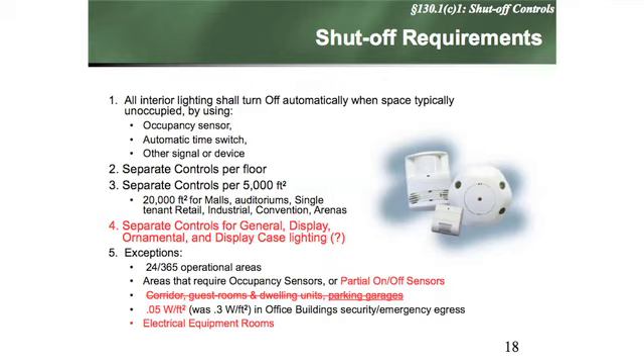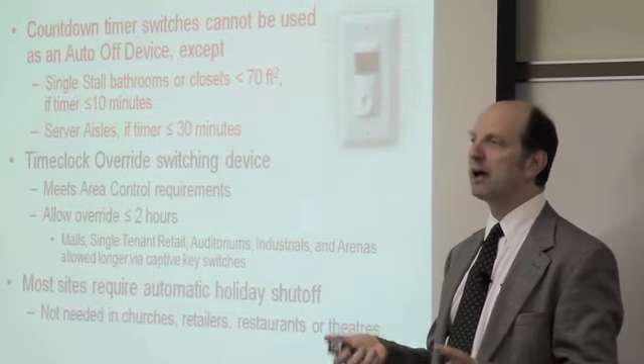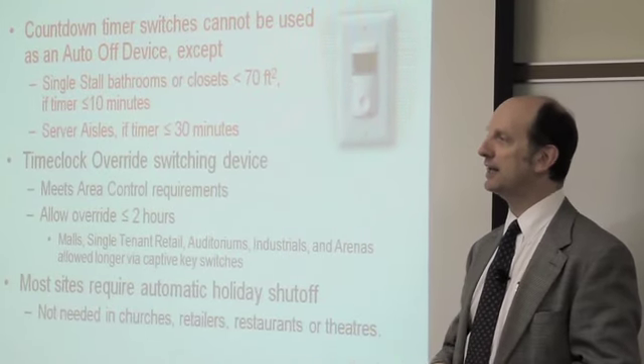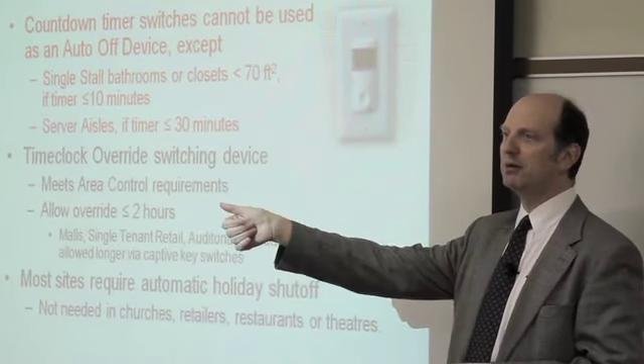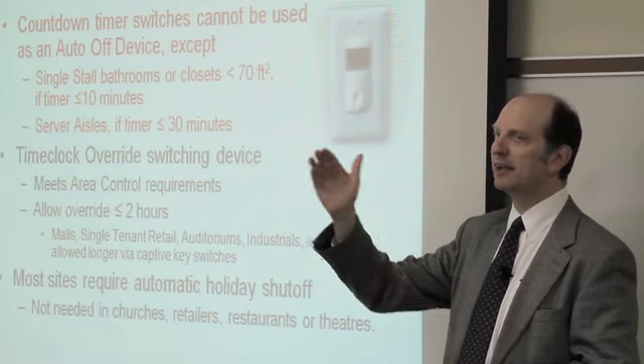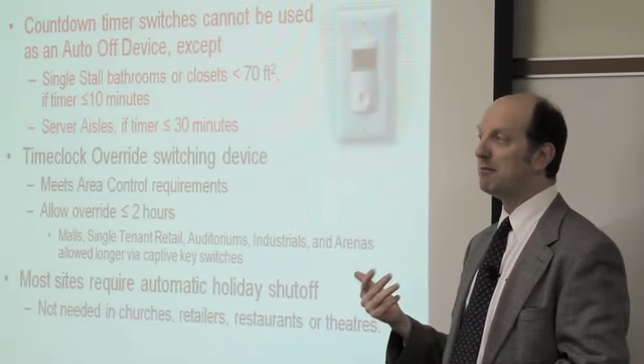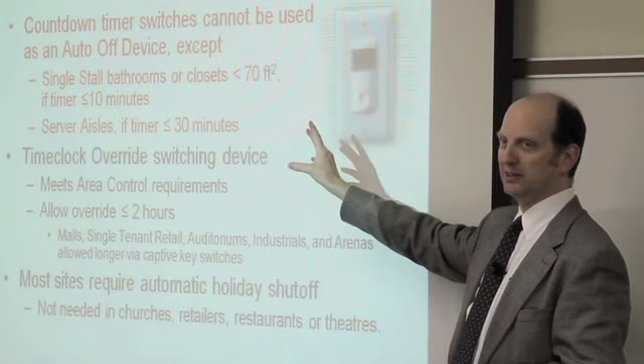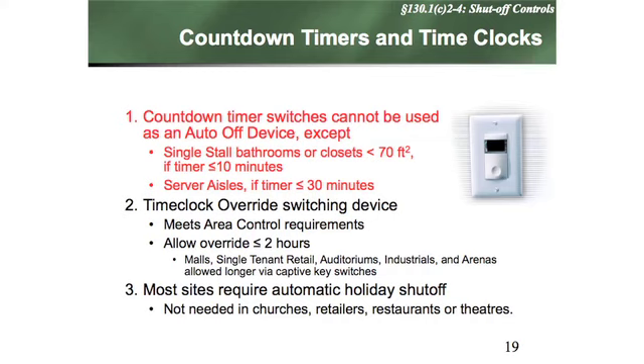And then we get into this whole idea of partial on and off sensors. I don't know about you, but I always thought of timer switches as being the most logical lighting control device in the world. You turn it on for 30 minutes, and then 30 minutes later, tick, tick, tick, tick, it turns off, right? Somebody really has a problem with timer switches. So it is now listed in the code that you can't use timer switches, countdown timer switches, for interior building spaces. We're going to include this in the code now, make it very clear.